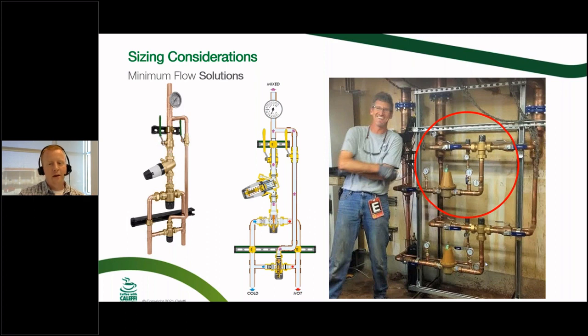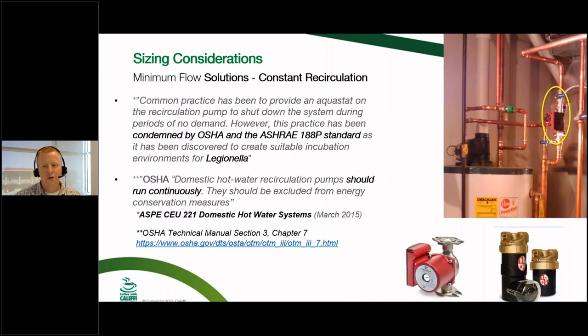But another scenario, and another tick in the box for continuous recirculation, is minimum flow requirements. If you have your recirc piped properly, balanced properly, and set up properly, the recirculation can make up for the minimum flow requirement of the mixing valve. So instead of a high-low assembly, you could have a single mixing valve with your recirc running all the time, and everything's going to be perfect. In another scenario, we talked about Legionella. Running that recirc all the time will help manage that Legionella risk to some extent, because you're eliminating that stagnant water condition as much as possible.